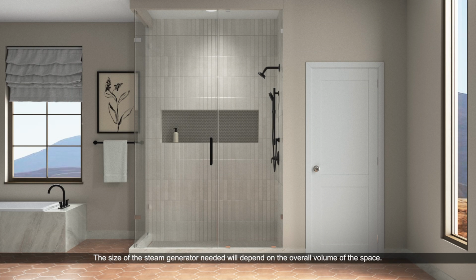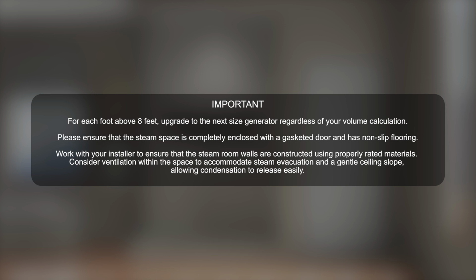The size of the steam generator needed will depend on the overall volume of the space. The recommended ceiling height for steam spaces is 8 feet, with a maximum of 10 feet. Important: for each foot above 8 feet, upgrade to the next size generator regardless of your volume calculation.